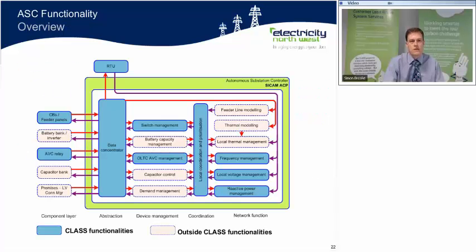Okay, so finally, just an overview of the autonomous substation controller. The functions which we're using here on the class project are a subset of what's available, and the focus is on the frequency management, local voltage management, and the reactive power to deliver higher voltage control. We do this through controlling circuit breakers and also the AVC relay set points. And I'm now going to hand over to David, who's going to talk about the class customer engagement.